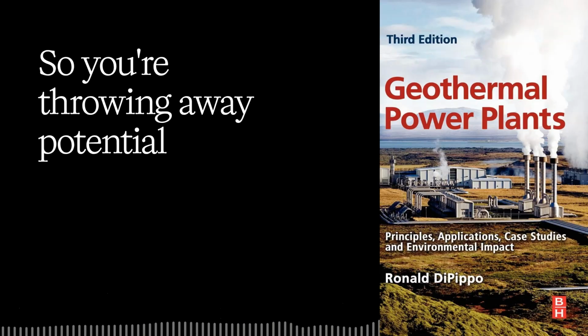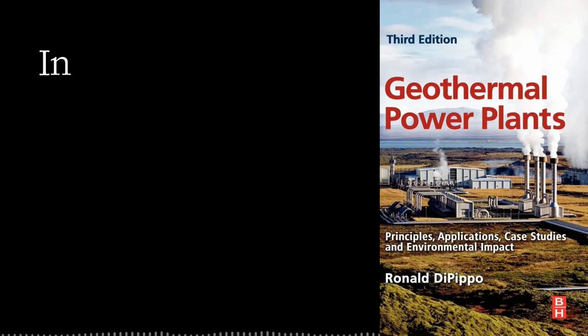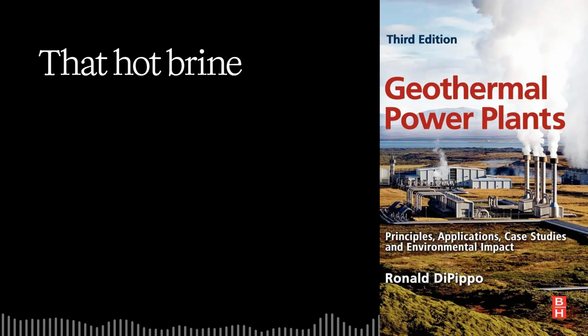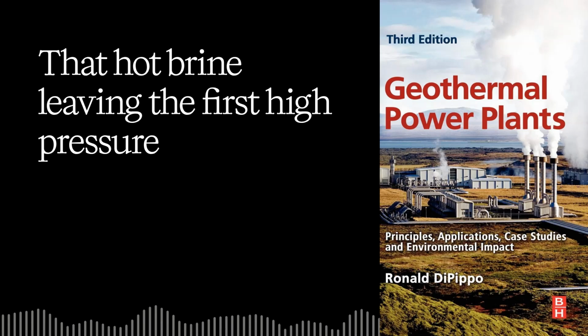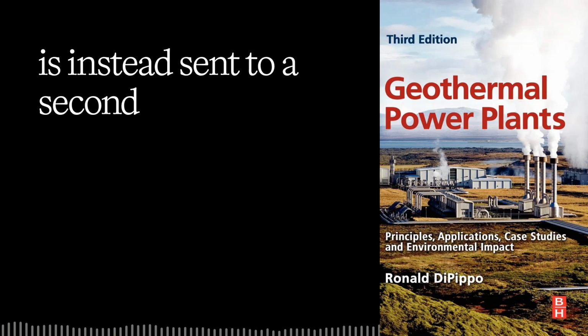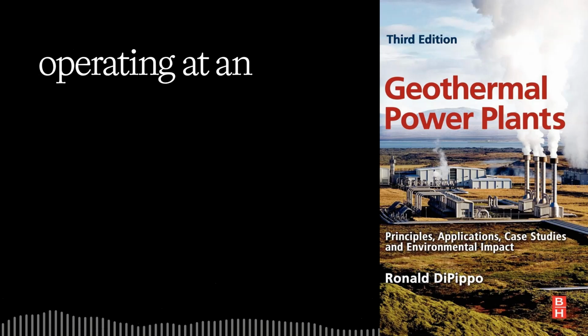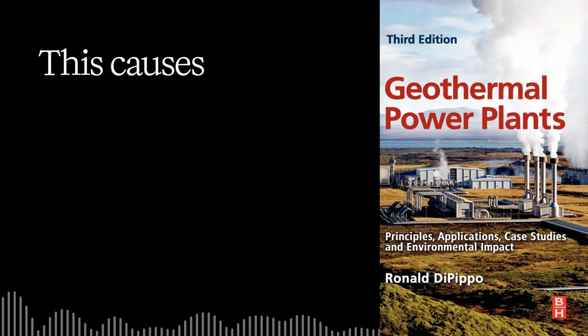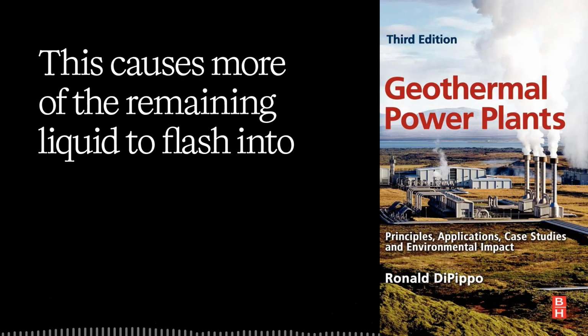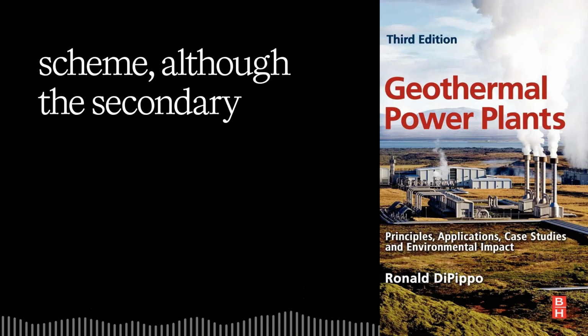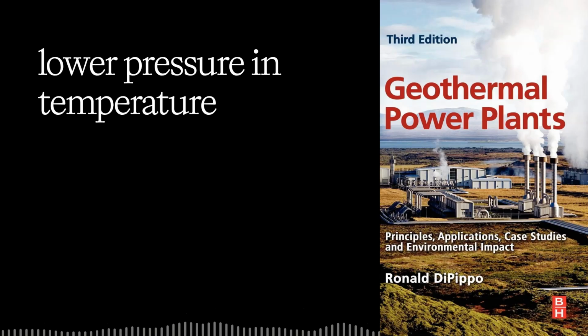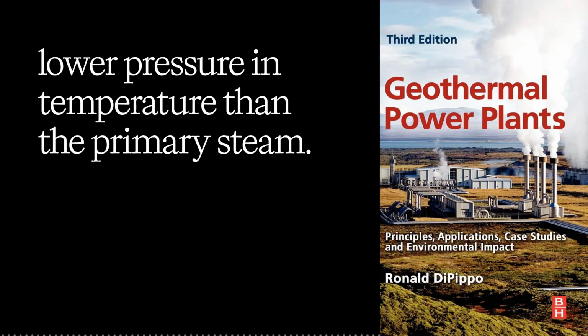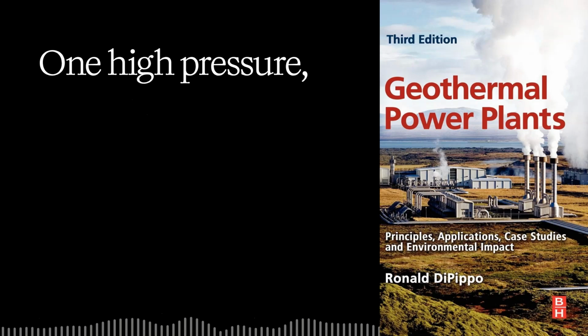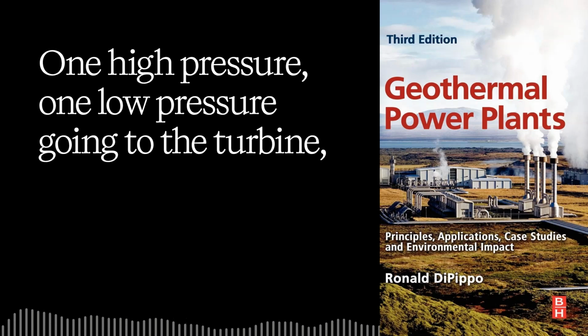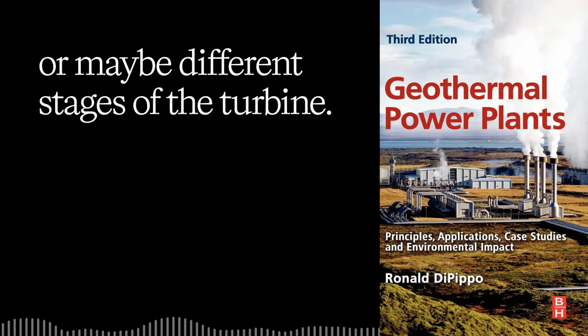So you're throwing away potential energy. You are. In a double flash plant, that hot brine leaving the first high-pressure separator is instead sent to a second flash vessel, operating at an even lower pressure. This causes more of the remaining liquid to flash into steam, although the secondary steam will be at a lower pressure and temperature than the primary steam. So you get two streams of steam, one high pressure, one low pressure, going to the turbine, or maybe different stages of the turbine. Exactly.